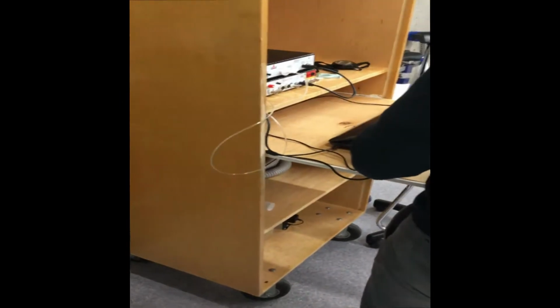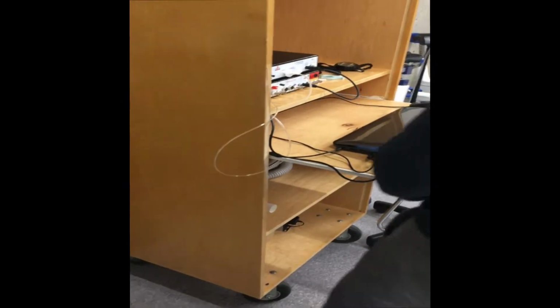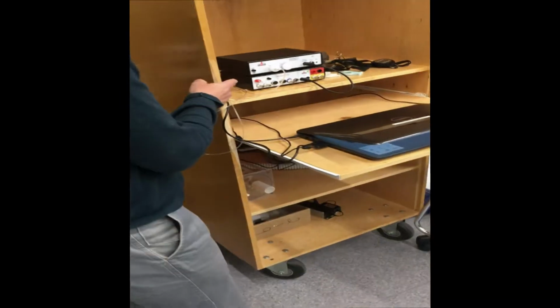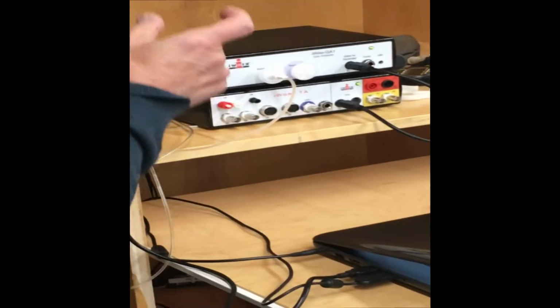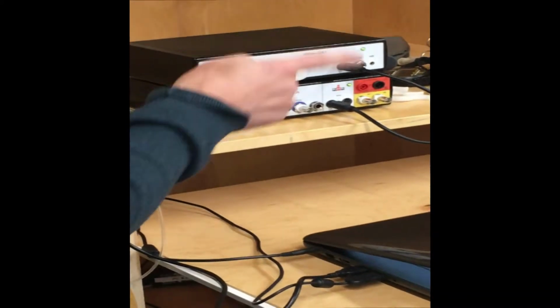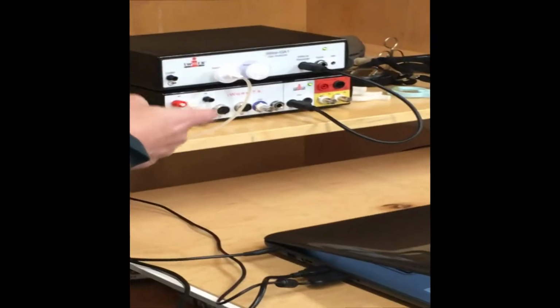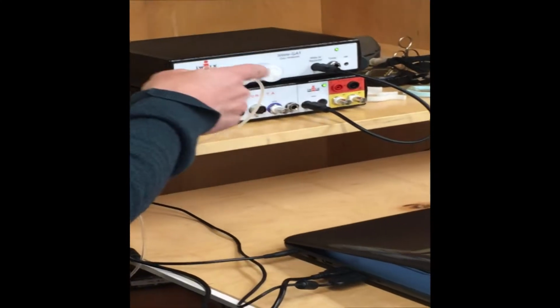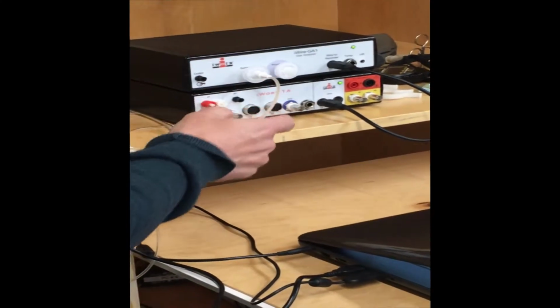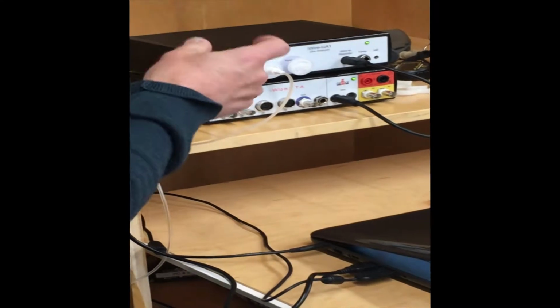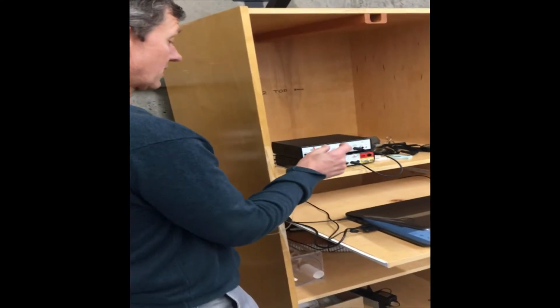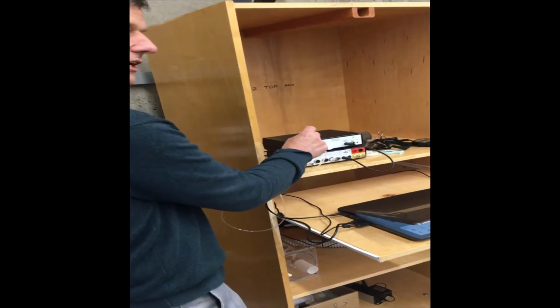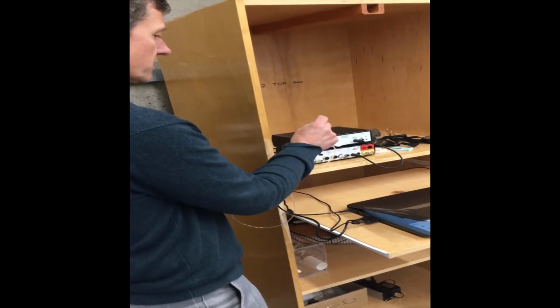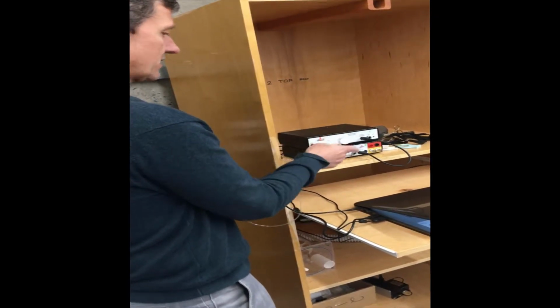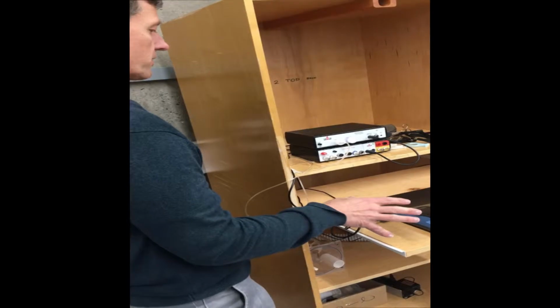So the first thing we need to do is calibrate our gas analyzer. So this is the gas analyzer. We haven't used this before. This is an iWorx gas analyzer that we're able to hook into the iWorx TA. There's just a simple iWire connection that goes from the gas analyzer to the TA. This gas analyzer is a little bit different than other gas analyzers because it doesn't display the value for the oxygen and CO2 concentration, but we're able to take that information and display it on our computer.